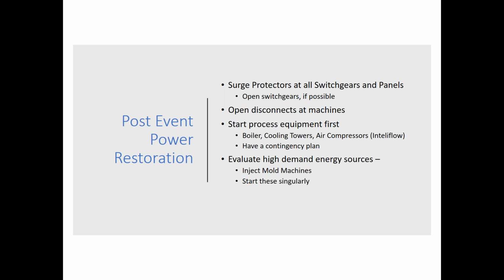My suggestion is to have a contingency plan for your critical equipment listing. If you lose power or lose a whole bus, you can go get a generator, bring in rented cooling towers, boilers, any equipment necessary for your process. You need that plan so it doesn't shut you down.